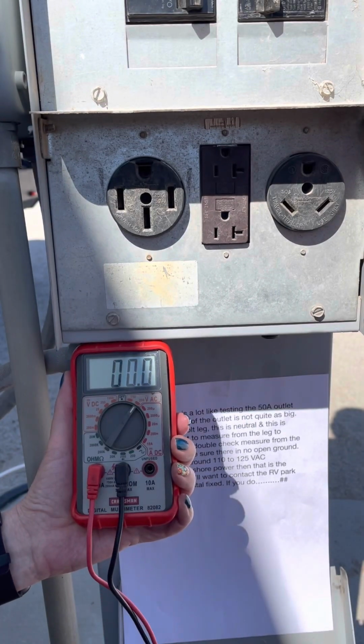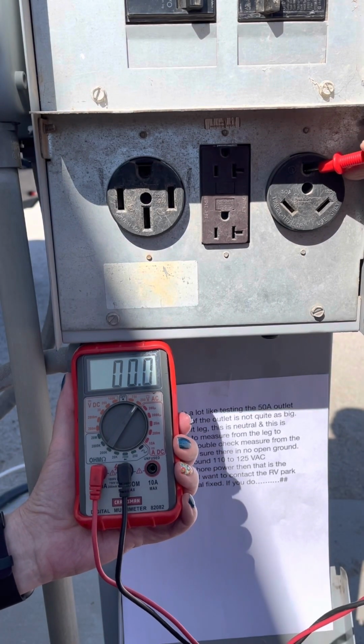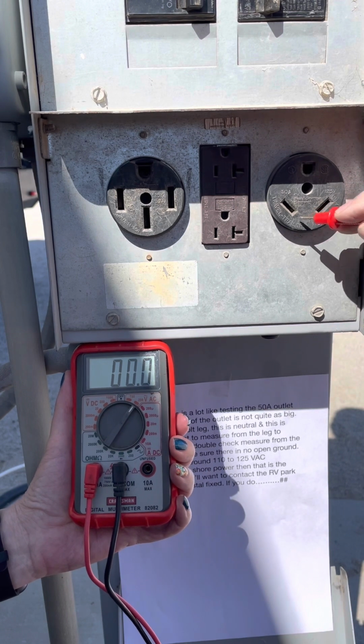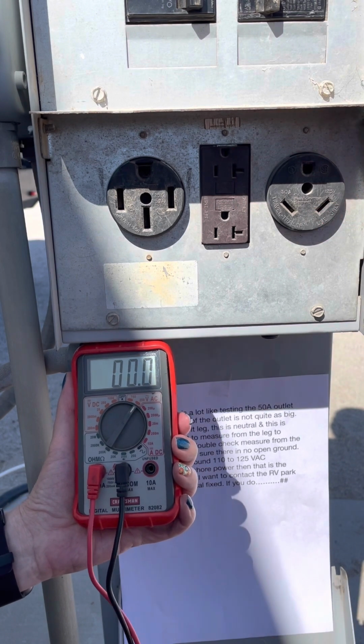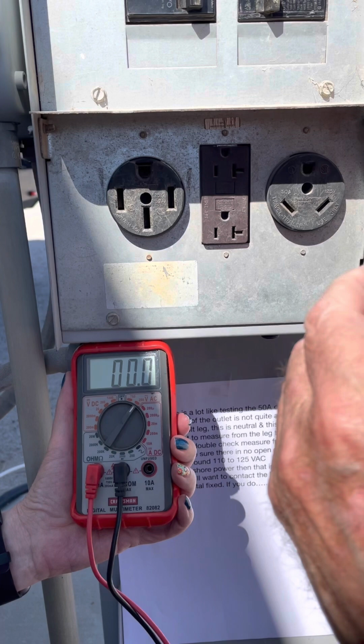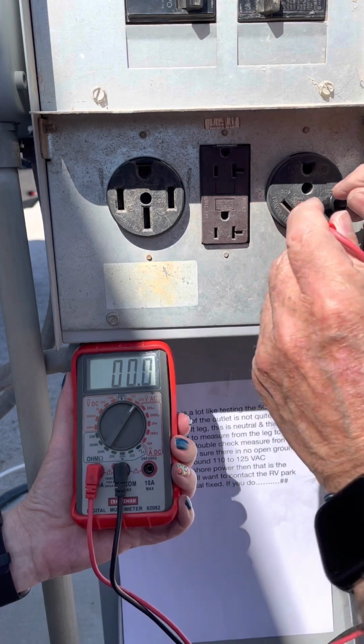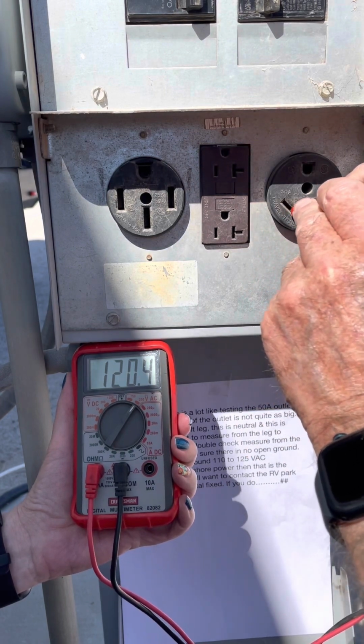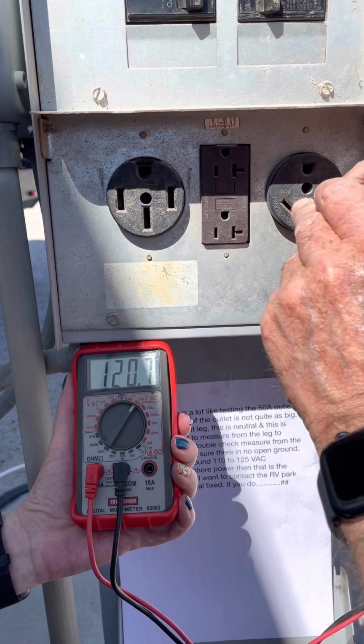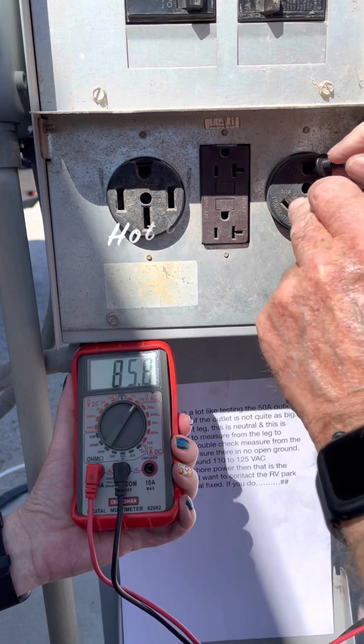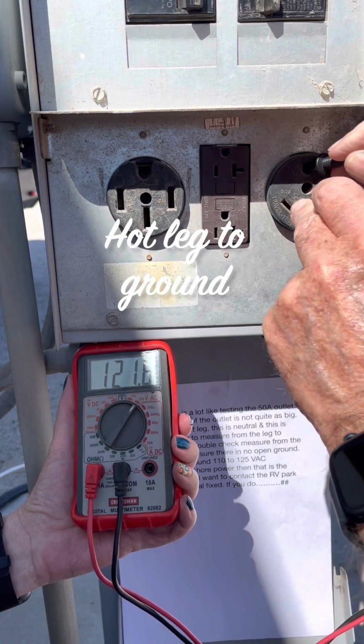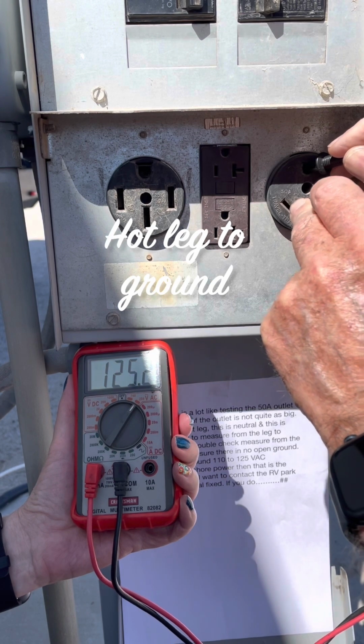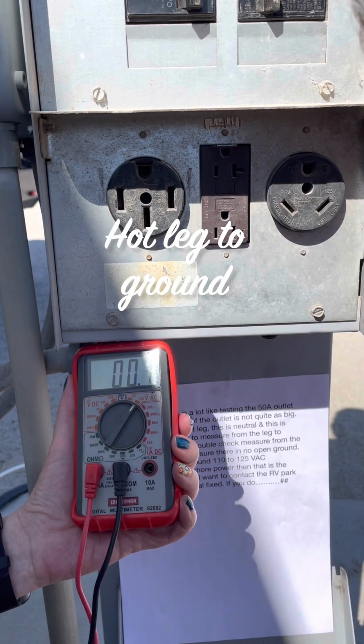So this is ground, this is hot, this is neutral. So we're going to measure from neutral to hot. Should get around 120 volts. And then we want to measure from hot to ground. This proves we don't have an open ground, and I have 120 volts.